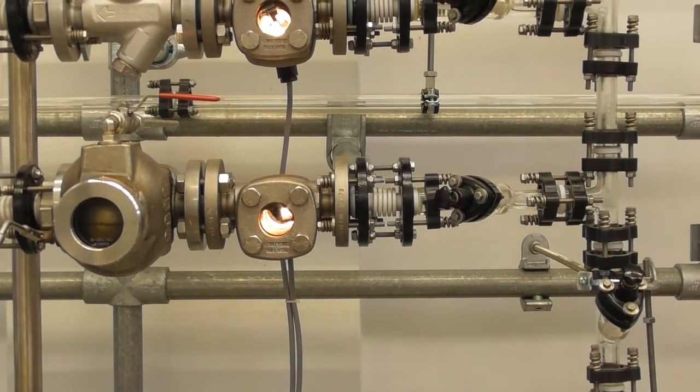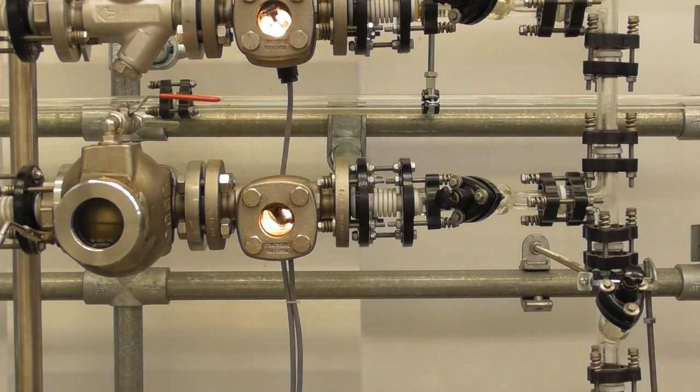Let's take a look at what happens if we run into a steam lock situation. I will now slightly decrease the pressure in the heat exchanger and this will unexpectedly lead to an unusual banking up of condensate.